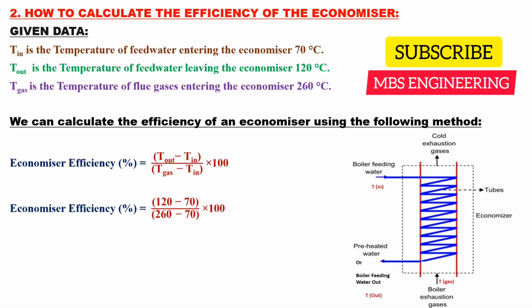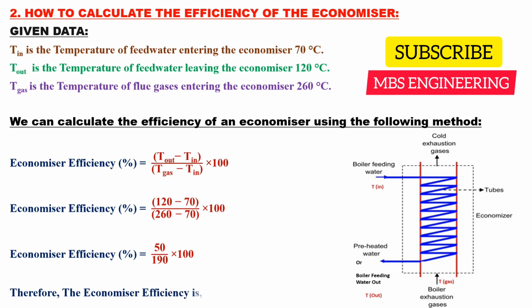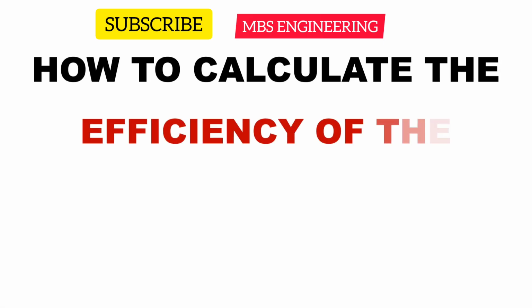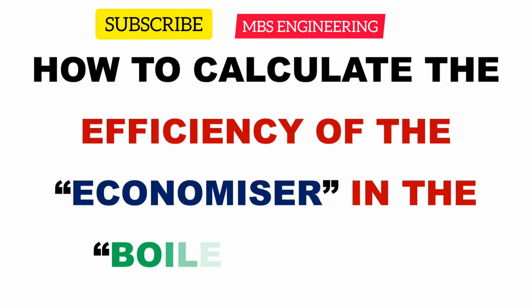The economizer efficiency in percentage is 50 multiplied by 100, and then the obtained value is divided by 190. Therefore, the economizer efficiency is 26.315%. We hope everyone learns and understands how to calculate the efficiency of the economizer in the boiler system.